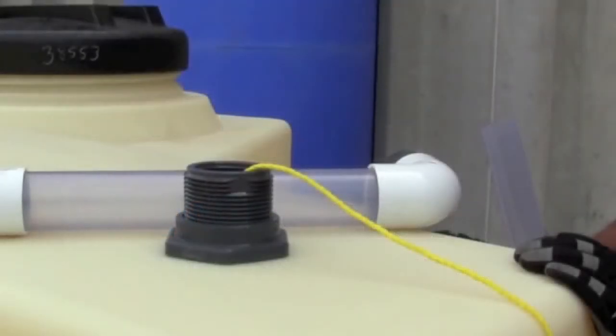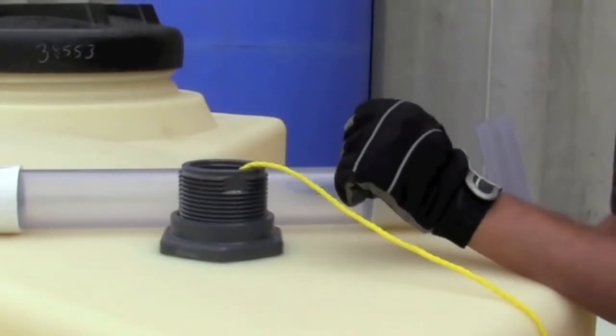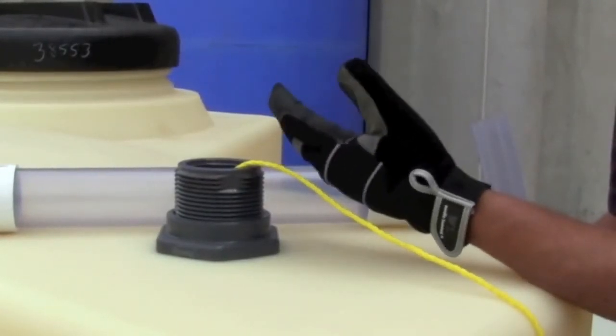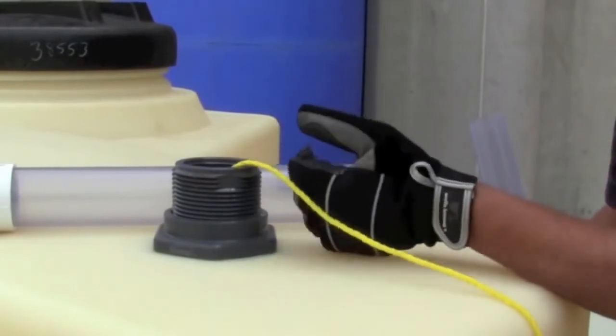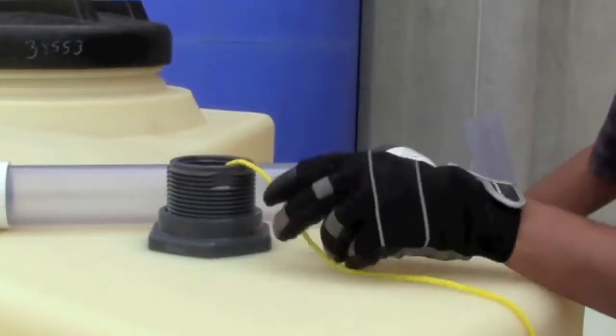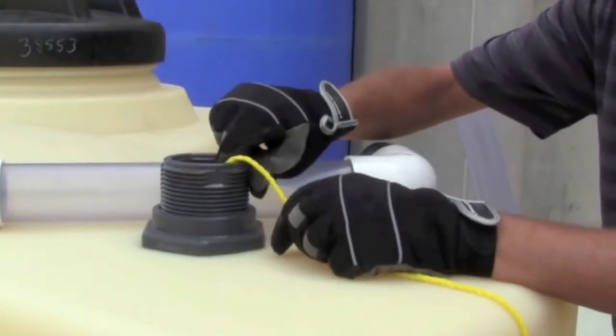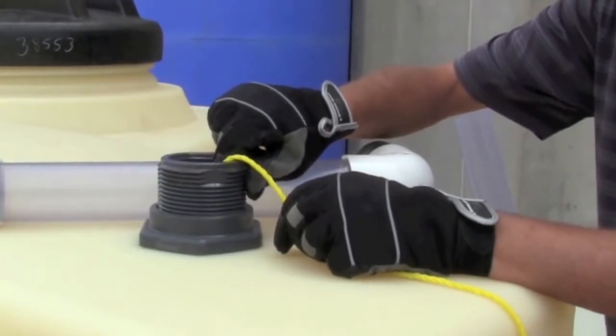You have the internal pipe for the reverse float installed on the back side of this bulkhead. There's two ways to achieve this. If it's safe and feasible to make an entry in the tank, you can go in and install it on the back side. If not, two people, by using the rope and rigging the pipe all the way over to the fitting and bringing it back up through is also a way to achieve this.